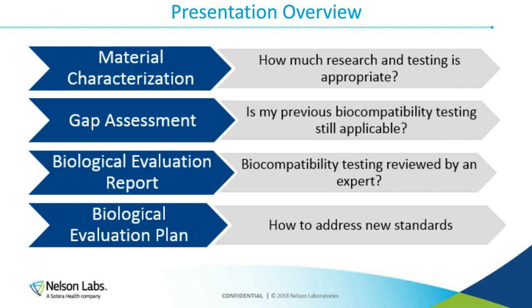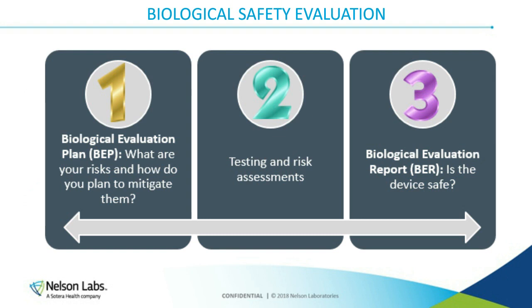And so now I'm just going to talk briefly about biological evaluation plans and how to address new standards. I want to step back and look at the big picture for your biological safety evaluation programs. This is really how the program should be designed according to the standards. We start in phase 1 with the biological evaluation plan, where you're identifying your risks, justifying what tests you're doing and not doing, how your testing is going to be performed, and extraction parameters, everything we talked about that is important for a biological evaluation report. We talk about that up front with justifications and rationale in our initial risk assessment.